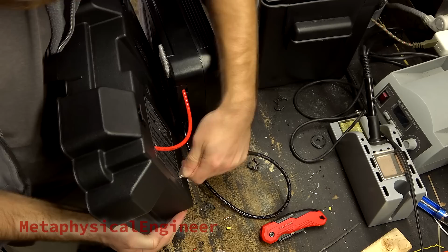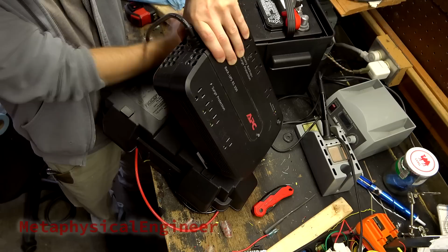Slight struggle to get the ring terminals through. 9/16-inch holes would have been better if I had a bit in that size. Extra armor on the cables can't hurt either, though I've confirmed the holes have been well deburred. Washers and proper torque on the connections for final assembly.